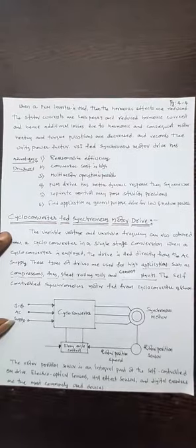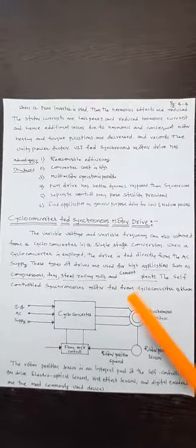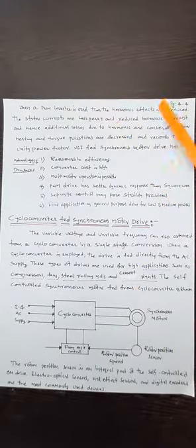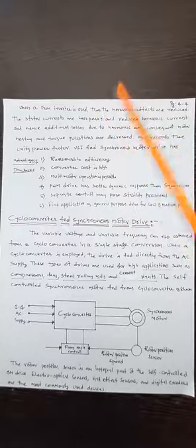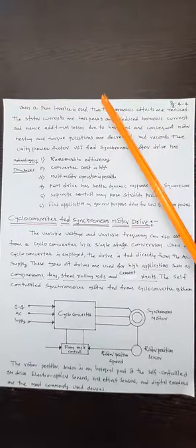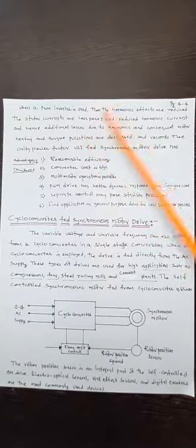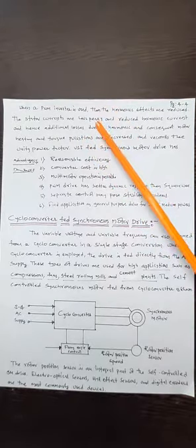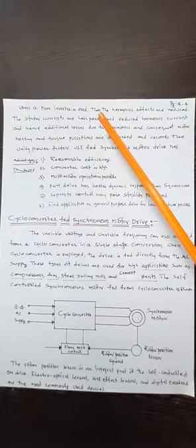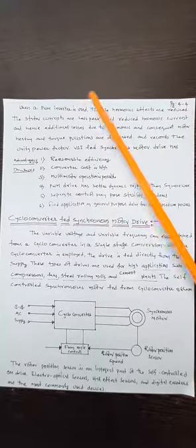So when a PWM inverter is used, the harmonic effects are reduced and the stator currents are less peaky. Peaky means maximum: during oscillations, it goes to a very high peak and then comes down, always oscillating, very peak and low. But that is not possible here.